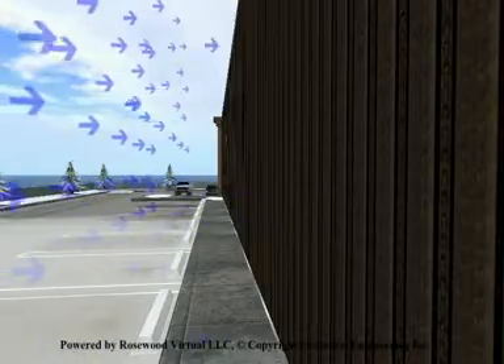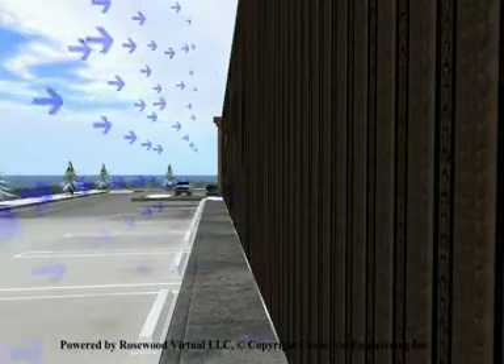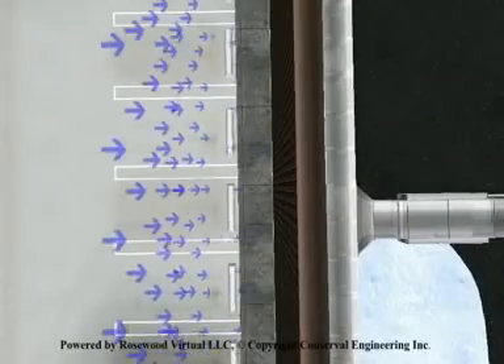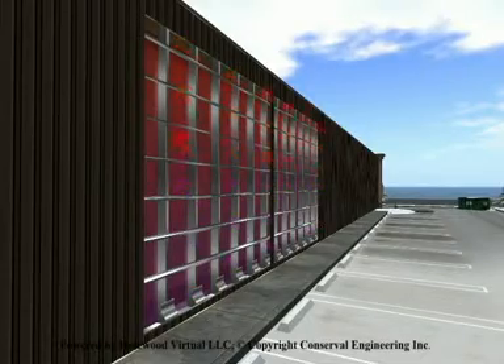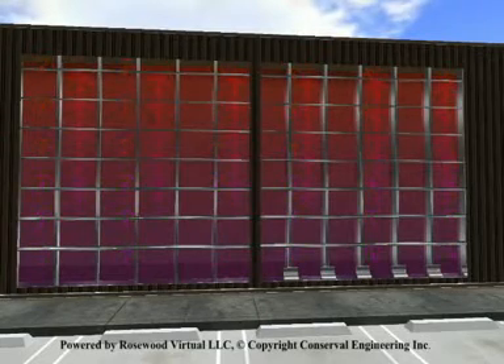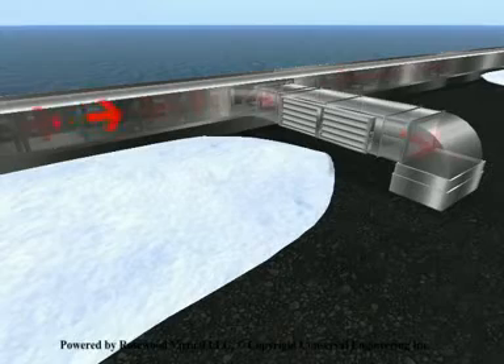Air is pulled through thousands of micro perforations in the surface of the SolarWall collector, where it picks up approximately 50% of the available solar energy. Air temperature continues to increase as the air rises inside the wall cavity. Air is then pulled horizontally once it reaches the top of the wall, where it is connected to the existing or planned ventilation system.